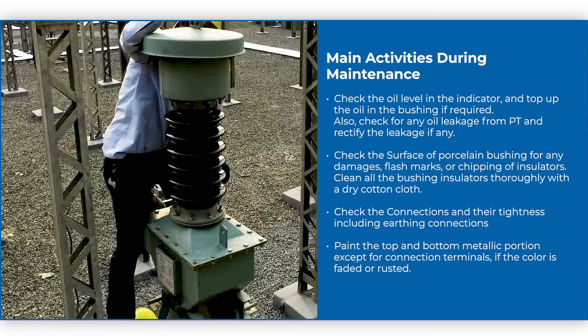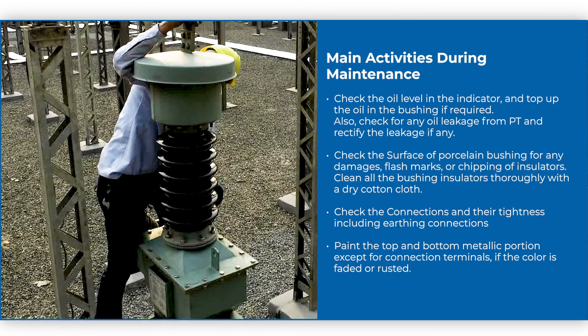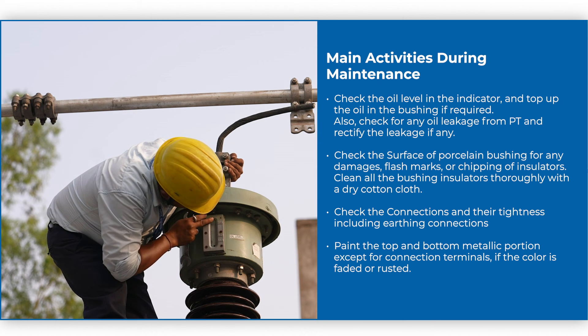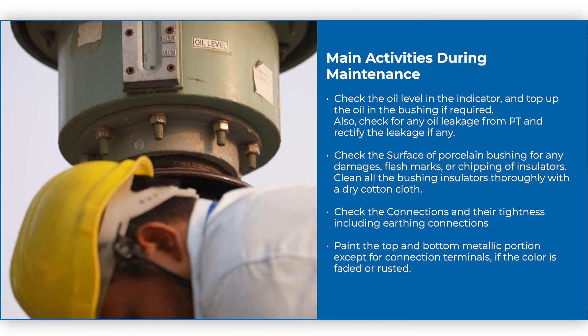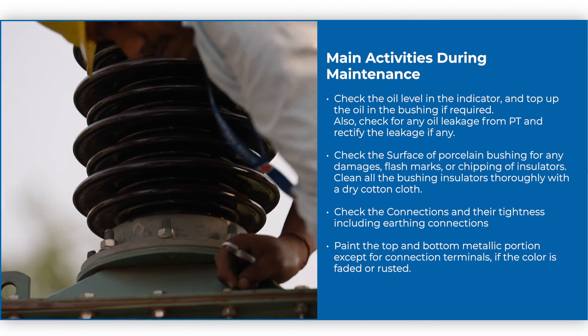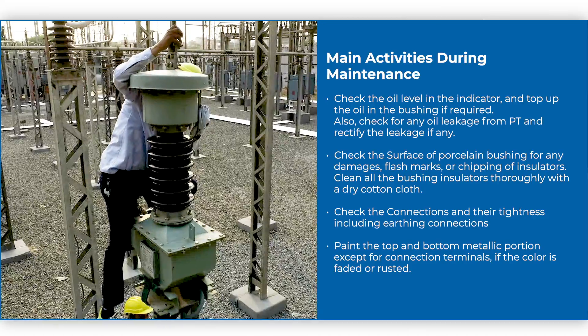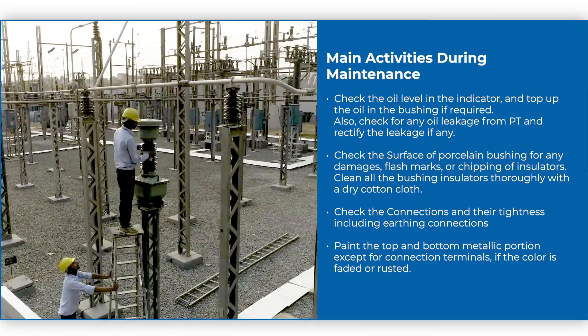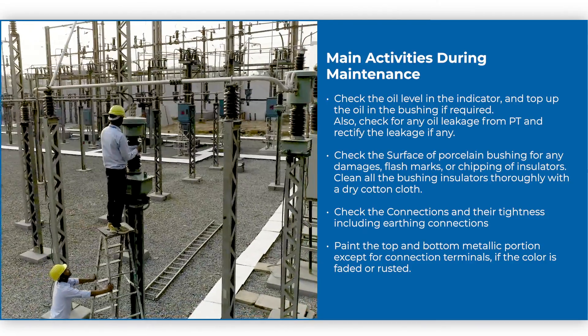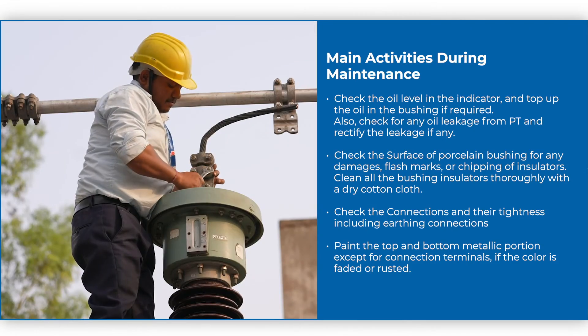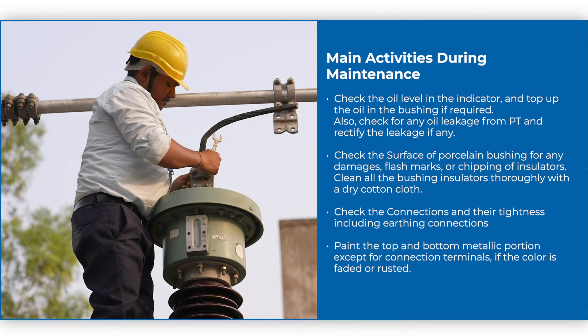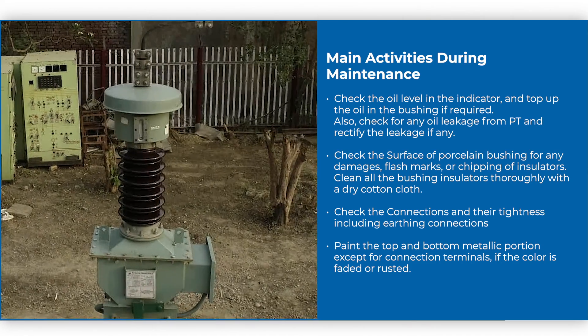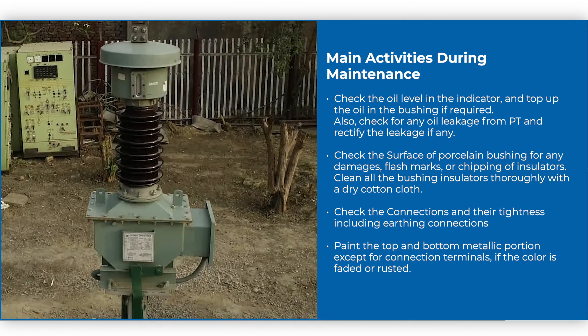There are many activities to be performed during maintenance. Check the oil level in the indicator and top up oil in the bushing if required. Check for any oil leakage from PT and rectify the leakage if any. Check the surface of porcelain bushing for any damages, flash marks, or chipping of insulators. Clean all the bushing insulators thoroughly with a dry cotton cloth. Check the connections and their tightness including earthing connections. Paint the top and bottom metallic portions except for connection terminals if the color is faded or rusted.